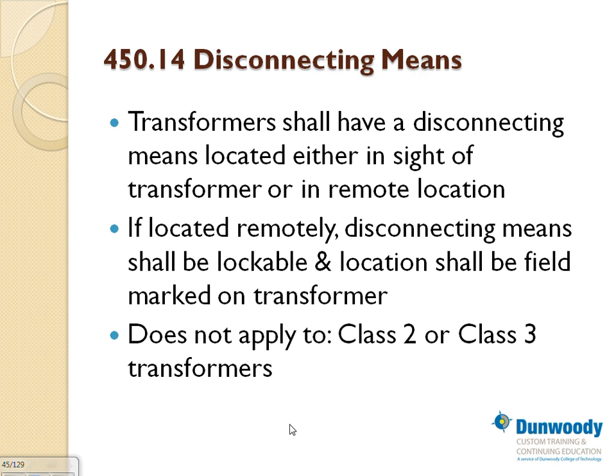So all this requirement is from 2011. Before 2011, it did not exist. There is an exception. Do you guys do low voltage? We have low voltage people who do low voltage fire alarm, security, phone, data. Yeah. Your tiny little Class 2 and Class 3 transformers are exempt, so don't worry about that. I know you're not going to sleep tonight because of that, but the control transformers for Class 2 and 3 circuits, control and signaling circuits, are exempt. So this is really not going to add anything to what we do.